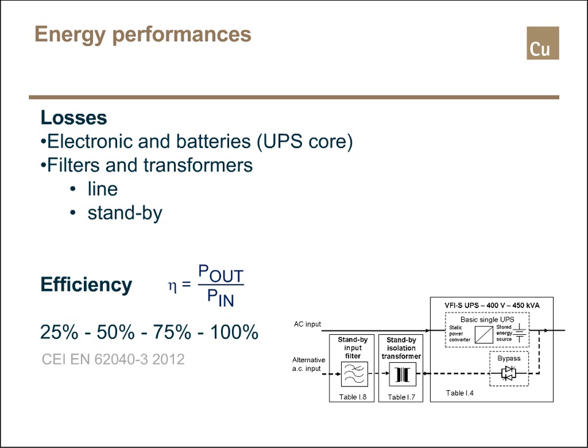Since 2012, with reference to the European standard — and also IEC 62040-3 — the efficiency of a UPS is defined classically as the ratio between output power and input power. In the past, this was specified only at 100% of the load. Now it is required to specify efficiency at four points: 25%, 50%, 75%, and 100% load. We could have expressed UPS energy performance as load and no-load losses, as we do with transformers, but for UPSs the standard uses efficiency defined in this way.